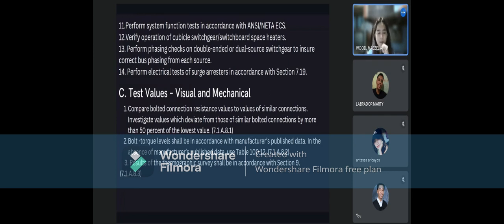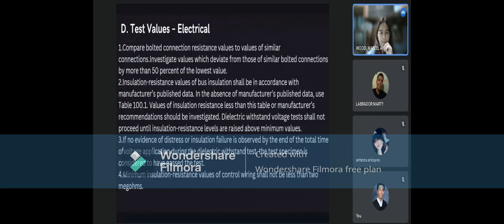7.1.A.8.1. Bolt torque levels shall be in accordance with manufacturer's published data. In the absence of manufacturer's published data, use Table 100.12, which will be seen later. Third, the result of the thermographic survey shall be in accordance with Section 9. D is the test values of electrical.